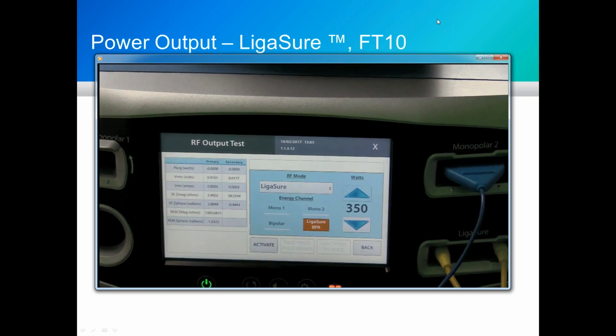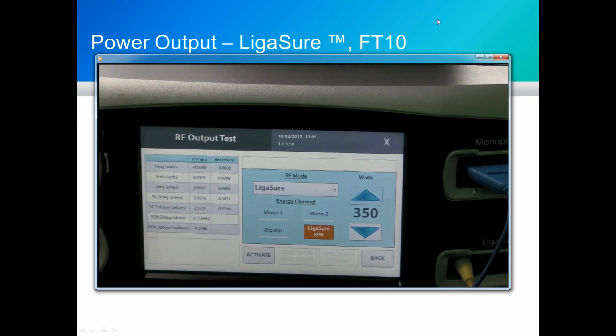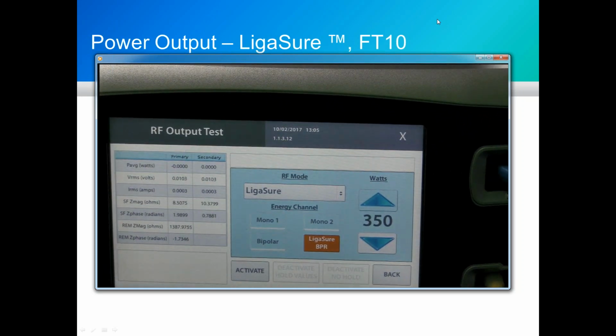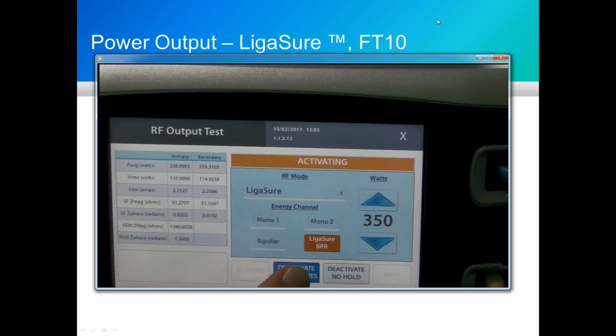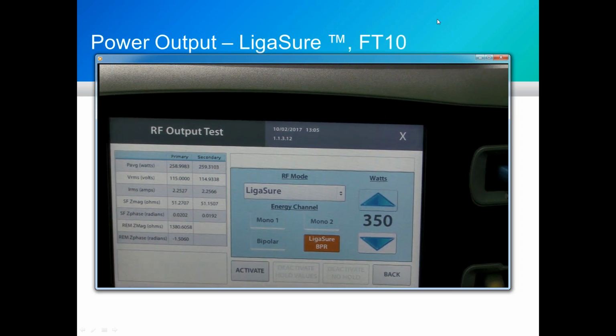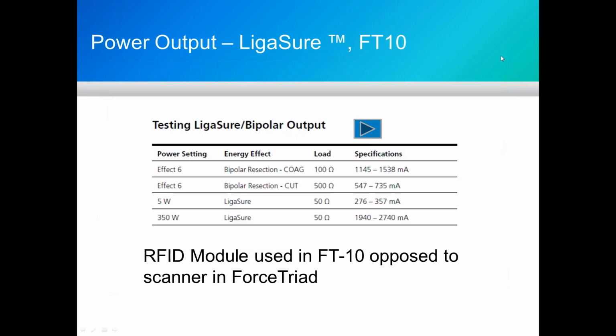Now I'm going to zoom in on the screen. Notice there's a primary and secondary column on the left-hand side. The secondary is a current transformer that is closest to the actual output port of the FT10. And second from the bottom, you see the REM Z-mag, and you also, 4 columns up, see the impedance that the generator is seeing. Very important, because if there's a lot of inductance or capacitance in your test circuit, that number will be different and could lead you to an improper calibration of the generator.